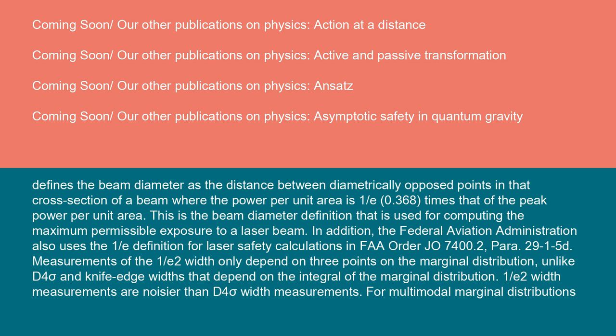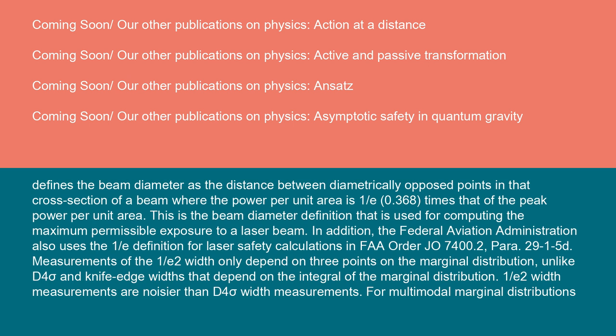Measurements of the 1/e² width only depend on three points on the marginal distribution, unlike D4 sigma and knife edge widths that depend on the integral of the marginal distribution. 1/e² width measurements are noisier than D4 sigma width measurements. For multimodal marginal distributions, a beam profile with multiple peaks, the 1/e² width usually does not yield a meaningful value and can grossly underestimate the inherent width of the beam. For multimodal distributions, the D4 sigma width is a better choice.